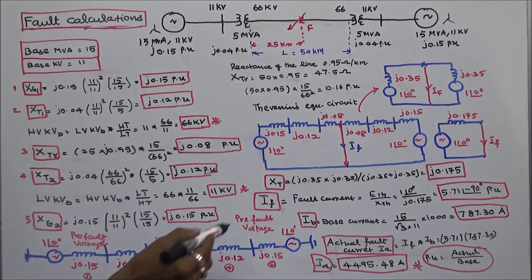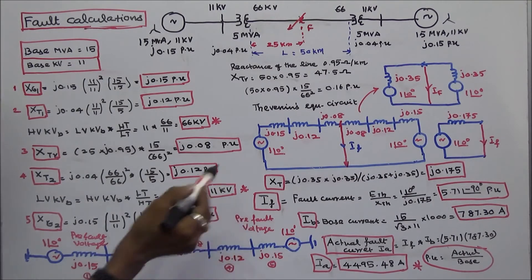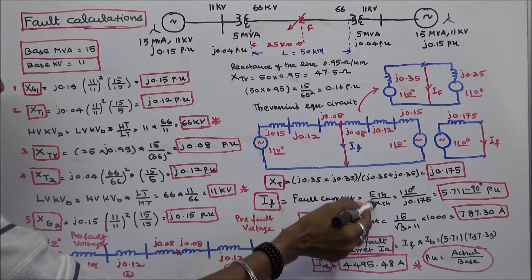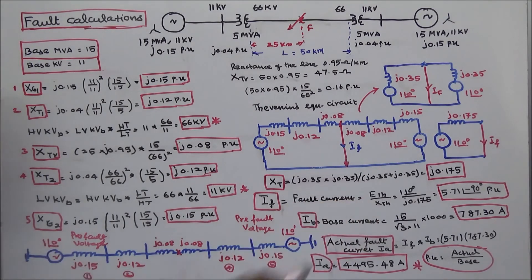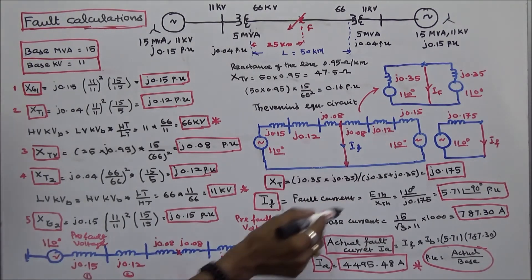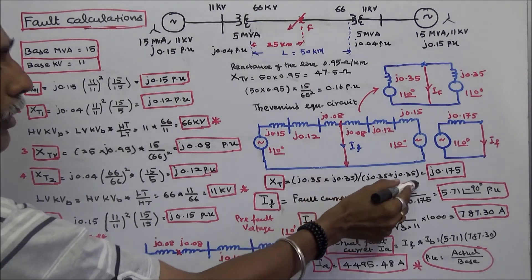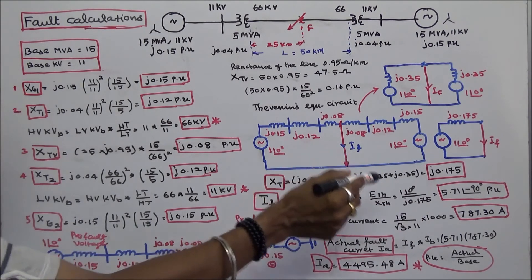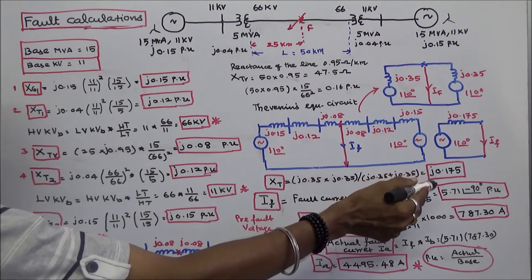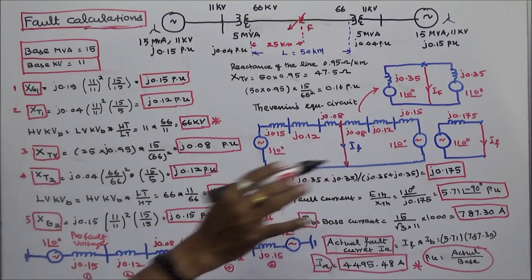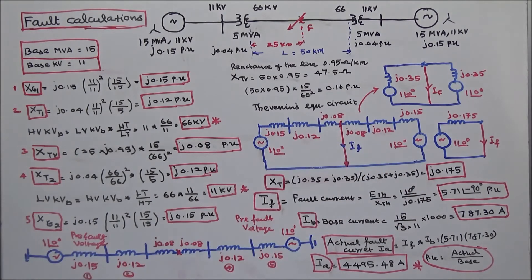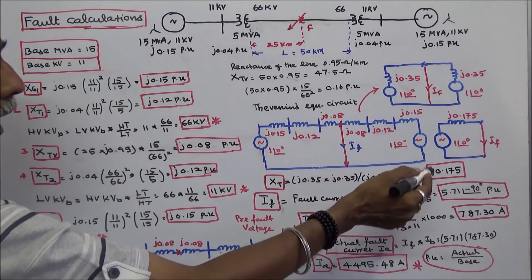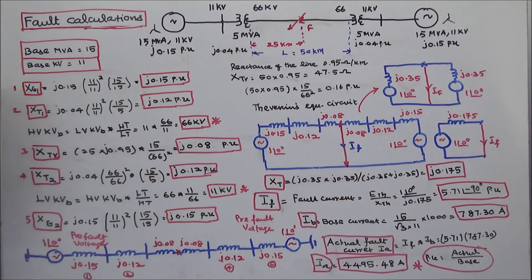We can now calculate the fault current. Fault current equals E_Thevenin divided by X_Thevenin = 1∠0° / J.175 = 5.71∠−90° per unit. So the per-unit fault current is 5.71∠−90°.